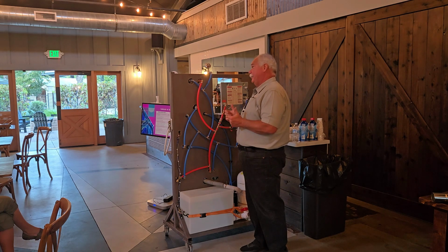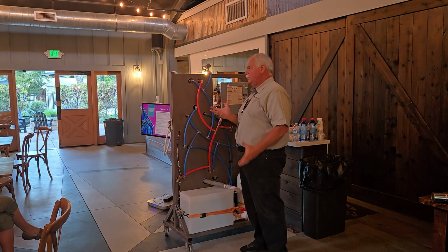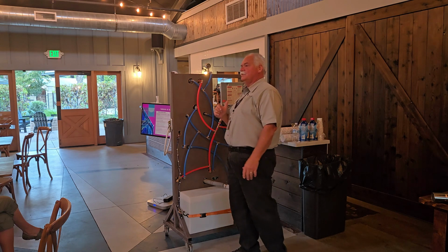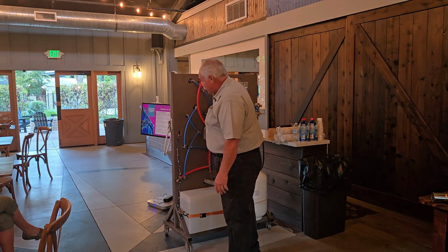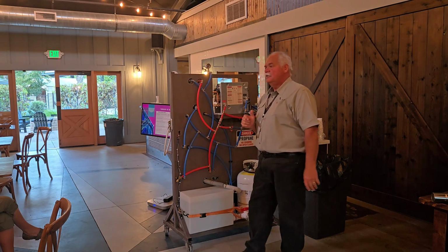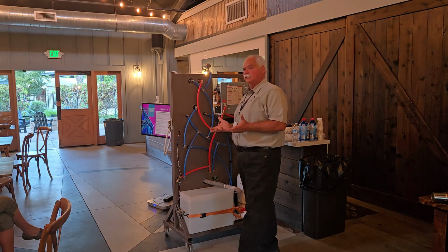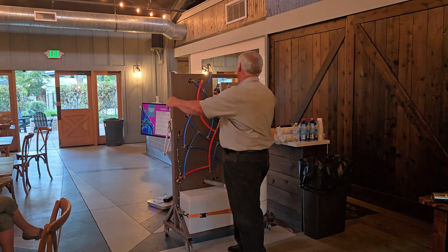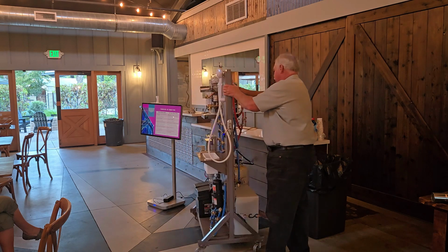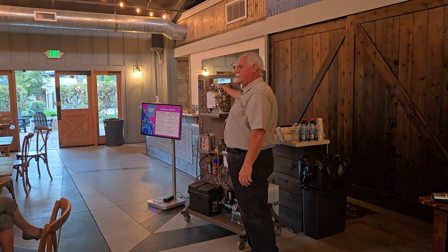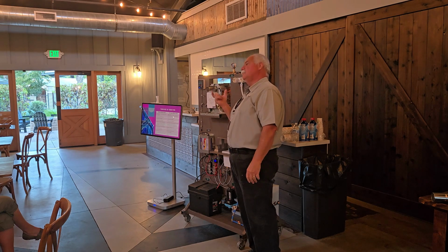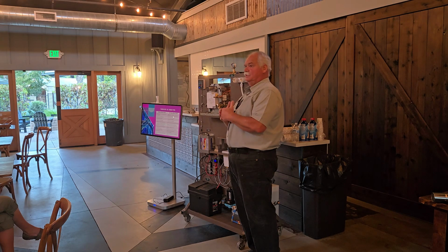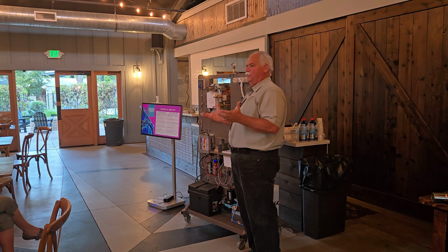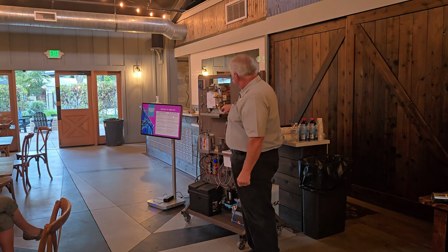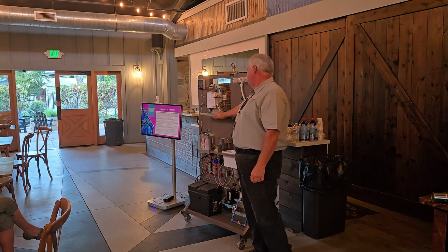So what happens if a mouse decided to build a nest in here, or you had some kind of insects or varmints or something, dust, that is going to block that airflow. Those holes are tiny. So if you don't get underneath there and make sure that that's clean, that airflow from that fan isn't going to be right. So people call me up and say, hey, I have a code, and it specifically says that it's my airflow sensor. Might be. That airflow sensor is really simple. It's a $12 part. But I'm going to tell them to get under there, see if you can get underneath there, and see if that's clogged up.